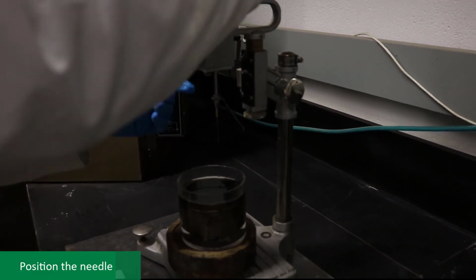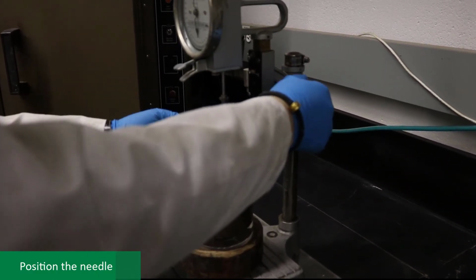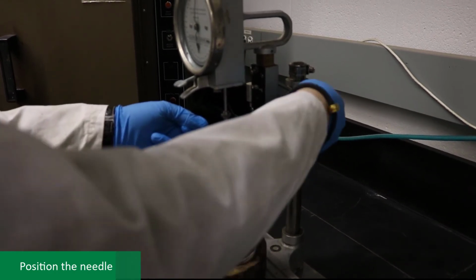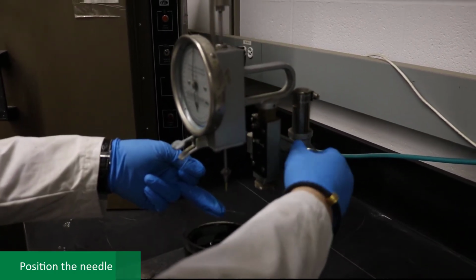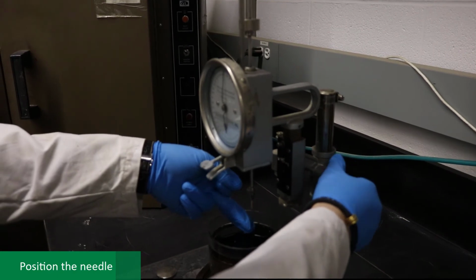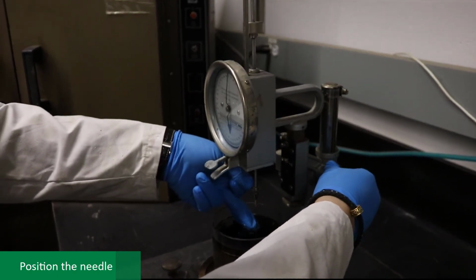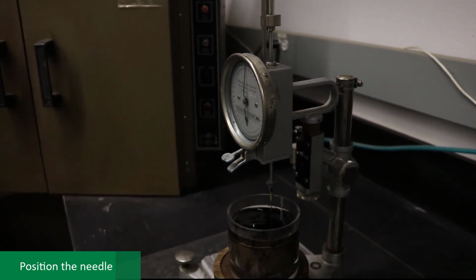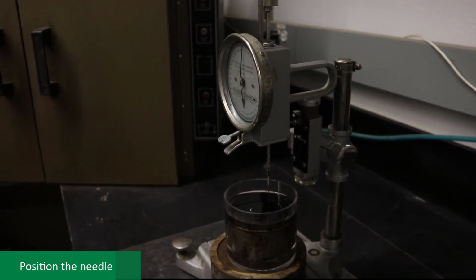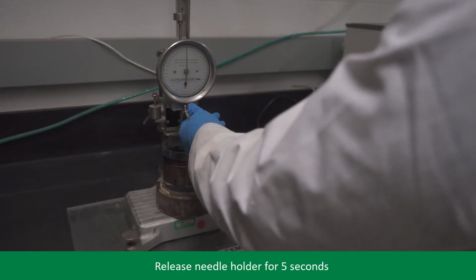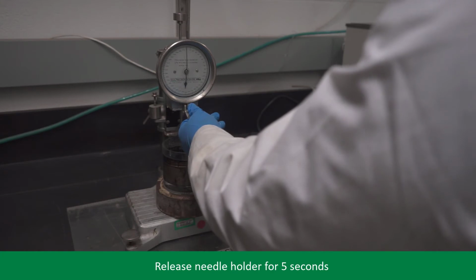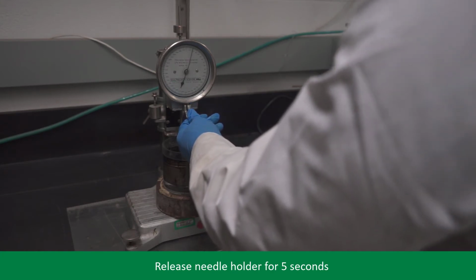Position the needle by slowly lowering it until the tip just makes contact with the surface of the sample. This is accomplished by bringing the actual needle tip into contact with its image reflected by the surface of the sample using a properly placed source of light. Quickly release the needle holder for 5 seconds and then adjust the instrument to measure the distance penetrated to 1/10 of a millimeter.